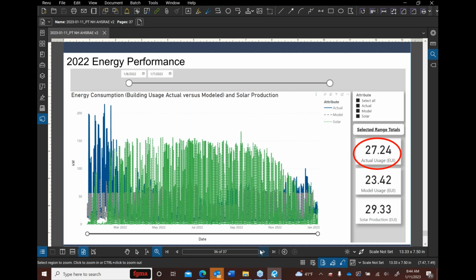Right. So I would add, those 2 months early in the year, there are lots of lessons learned that are built into this graph that we could go over. One, the BAS system. I mentioned we opened for school in August of 21. The BAS system was not set up to carry over from year to year. So it reset on January 1, which was a problem because our grant is contingent on proving that we are net zero through the BAS system.